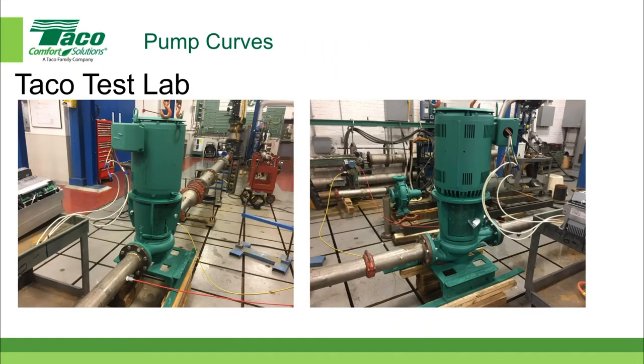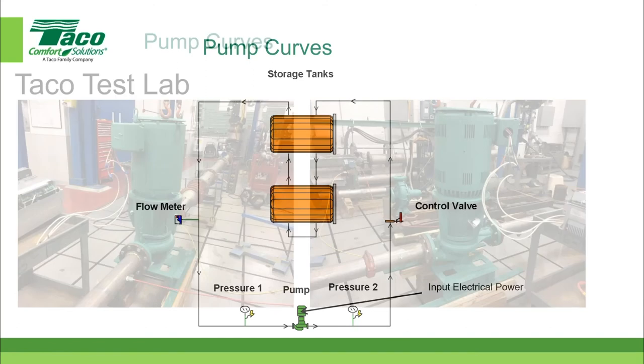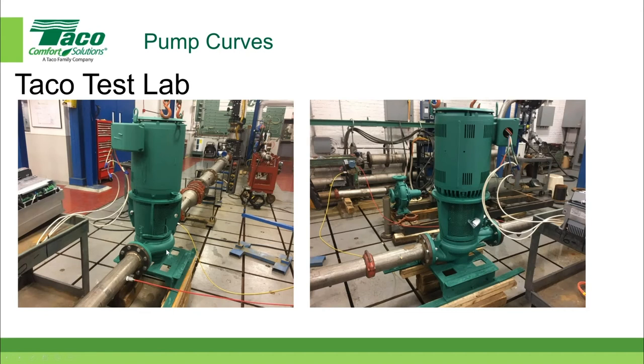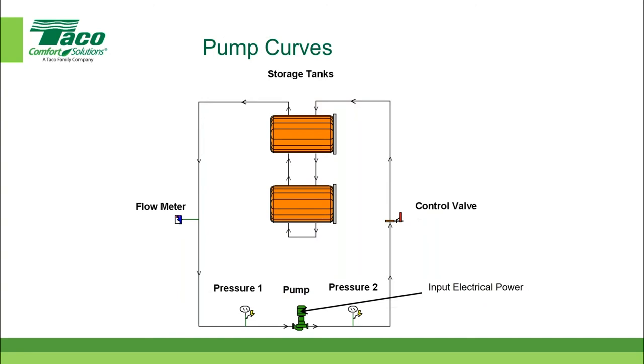Here you can better see the connections for the pressure taps. This is a vertical inline pump being set up for testing. There's a yellow tube connected to the suction side of the pump that measures the suction pressure, and a red tube connected to the discharge side to measure the discharge pressure. Way in the back there's a blue device that measures the flow in gallons per minute. We need four pieces of data: flow in GPM, suction pressure, discharge pressure, and the power consumed by the pump.